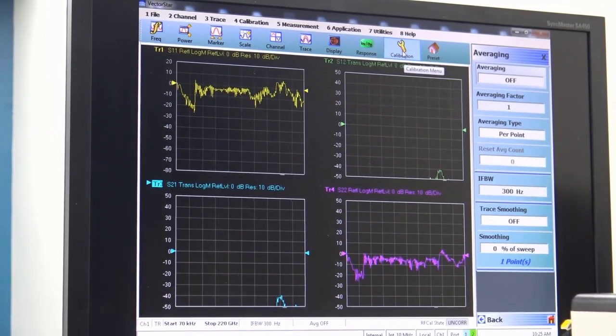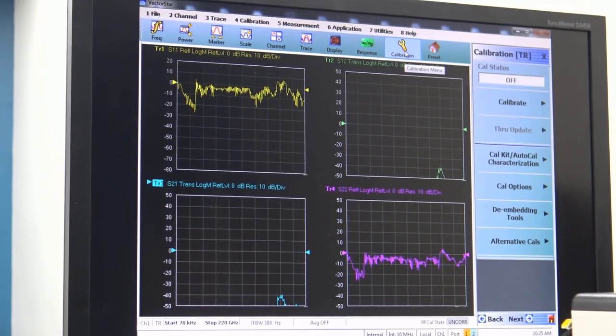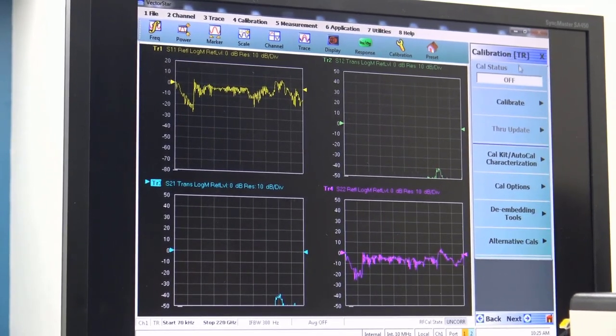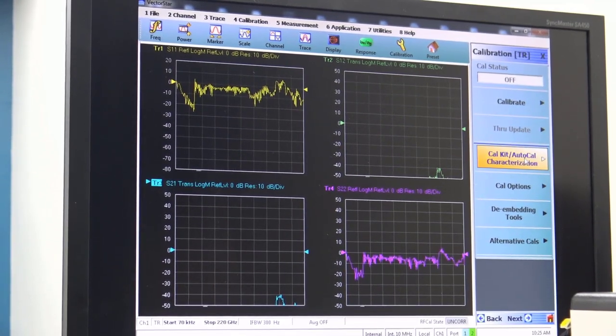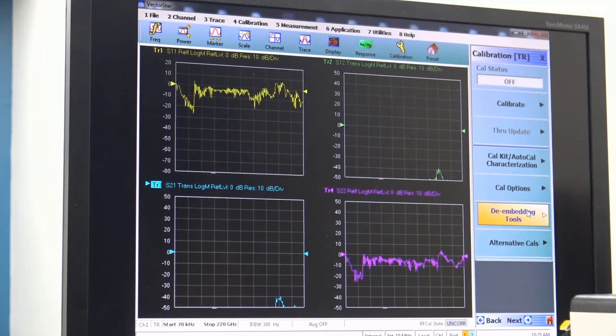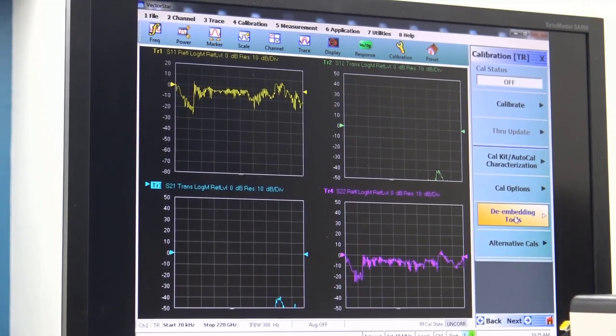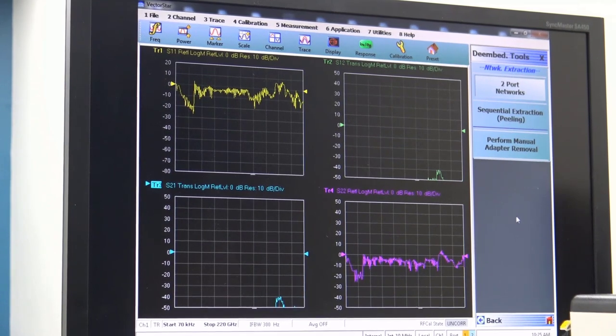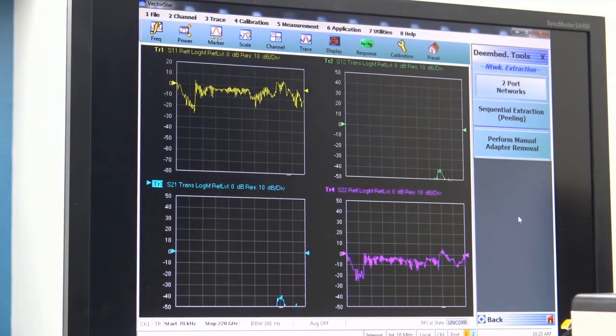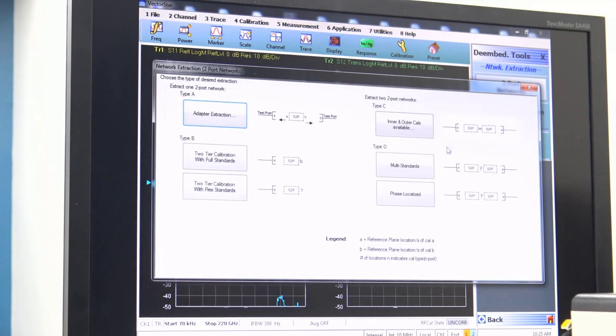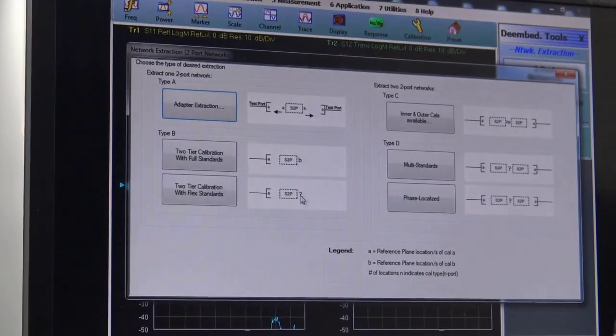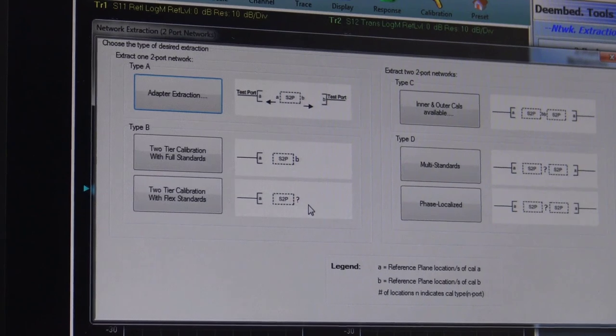Next we'll go to calibration and start setting up for that. In our calibration menu, we can go straight to calibrate. There are other options here that sometimes you might want to take advantage of. For instance, de-embedding tools. If you have fixtures that you may want to de-embed during this whole measurement process, we have a wide range of network de-embedding tools.